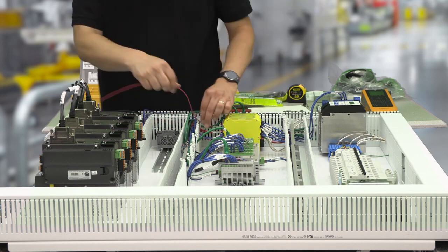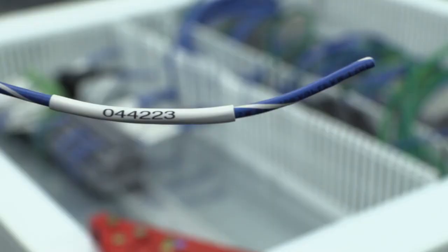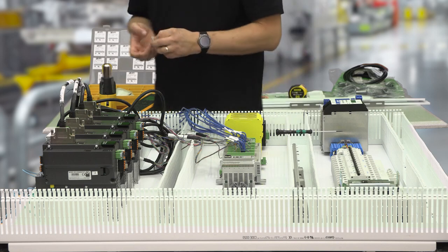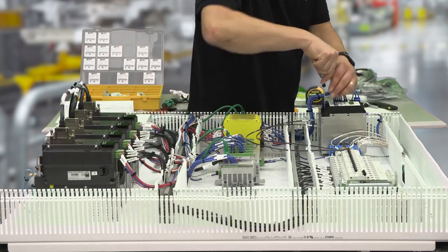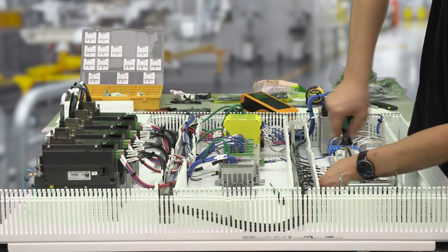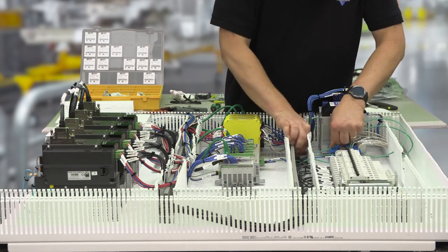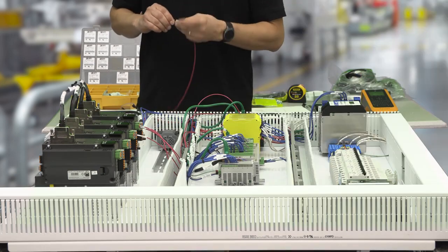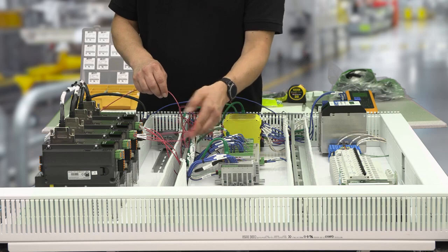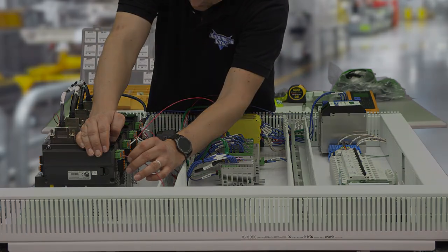be present. As you cut, strip, and crimp the wires, be sure to label them to match the schematics. Multi-core cables should be labeled differently to identify that they are distinct from single wires. Labeling individual conductors within a multi-core cable isn't necessary unless the cores are landing far away from the labeled end of the cable's jacket. Once the wiring is complete, it's time to test it.